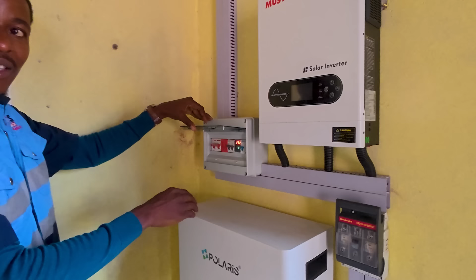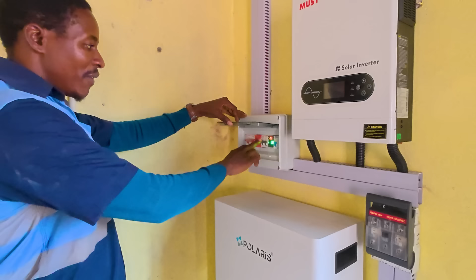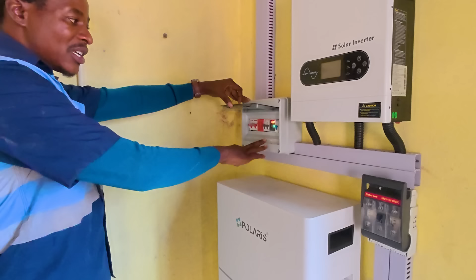You can interchangeably use this changeover switch. For instance, up here is where our solar is. This is what I call an AVS, an adjustable voltage regulator or protector. If I put this switch down, there will be no power on the sockets coming from the solar side. If there's a generator or utilities on the downside, then electricity or the generator will engage. If you want to go back to solar, we just put it up like this, and you'll see that in a few seconds.